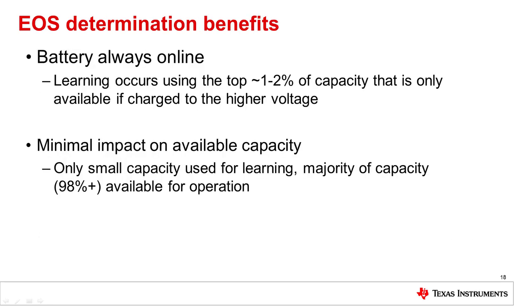Ultimately, the real benefit of this EOS algorithm is that you are able to keep a backup battery system online the entire time. The learning process uses only a very small amount of capacity — one or two percent typically — so you're not sacrificing much of the overall system capacity in order to allow this learning to occur. You still have 98-plus percent of the capacity available just in case a backup event happens, even right in the middle of a learning pulse.